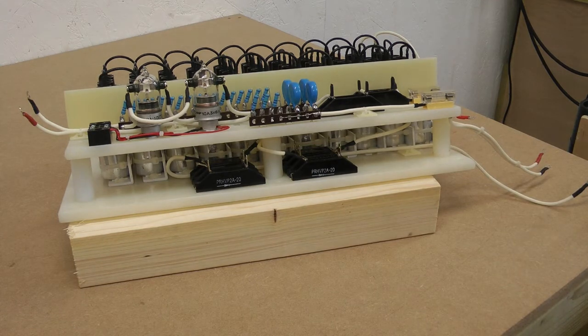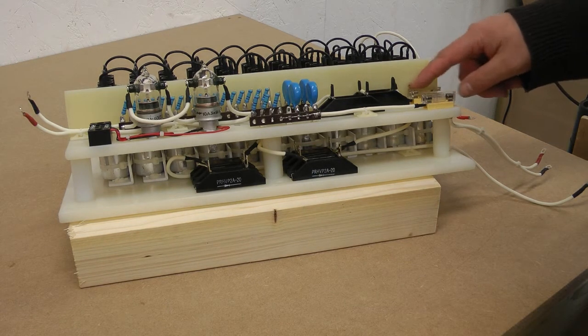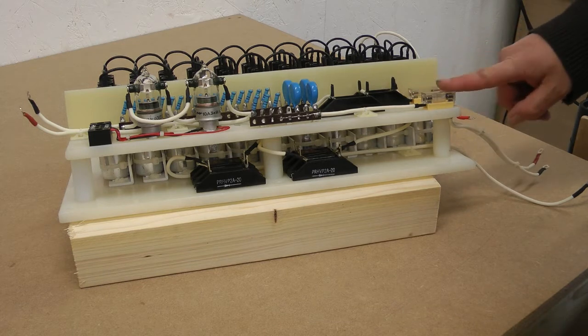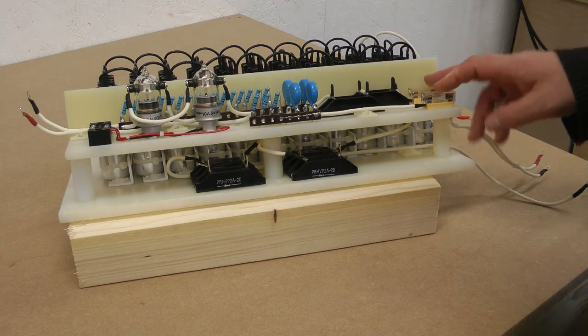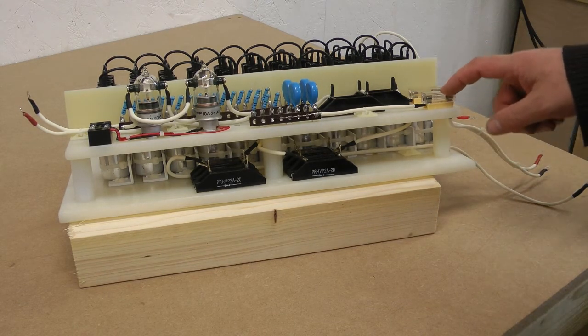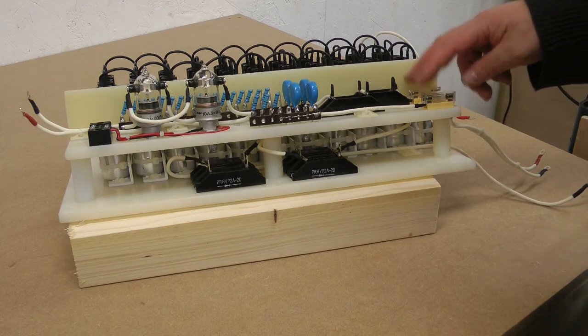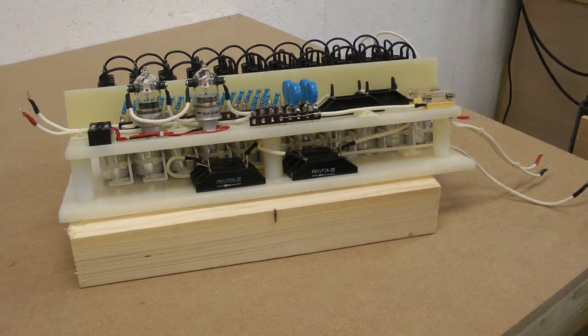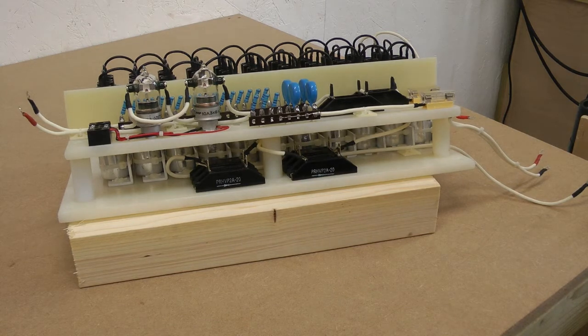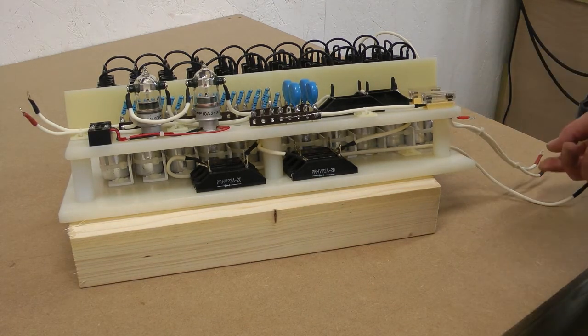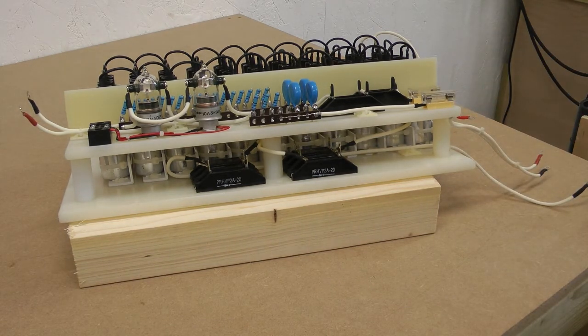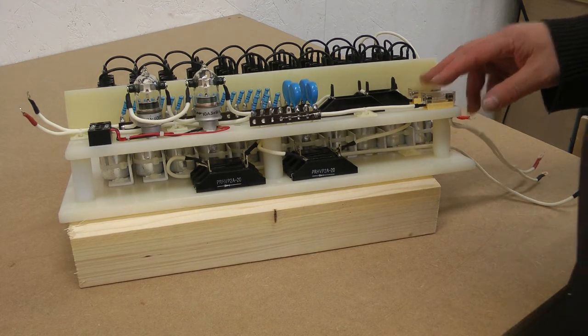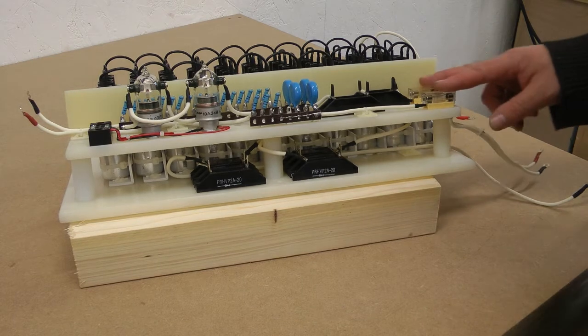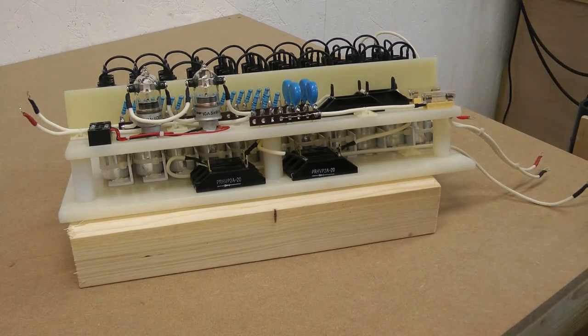So putting a fuse both in the incoming and in the outgoing, because you don't know where the arc over is going to occur. So it's important to have both ends, both directions, if you're running at negative HT or positive HT, where that arcs down to is going to affect which one of those is going to blow first. So having them both fused is important.